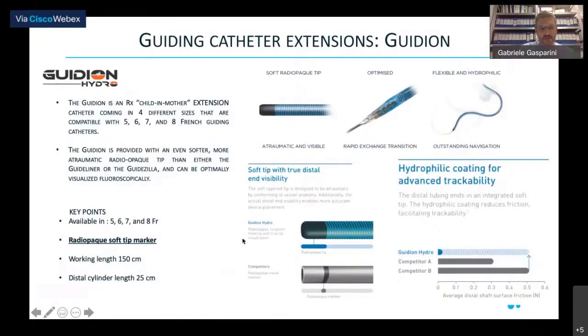This slide shows you the technical features of the Guidion guiding catheter extension. That is a guiding catheter extension with a very atraumatic tip compared to the competitors. This is due to the fact that the tip is radiopaque but made of tungsten. So if we remove the radiopaque marker from the guiding catheter extension and put in a tungsten tip, we can achieve a softer tip. In this case, this is the only guiding catheter extension without a metallic marker on its tip, but with a soft radiopaque tungsten tip. This is the main characteristic of the Guidion guiding catheter.